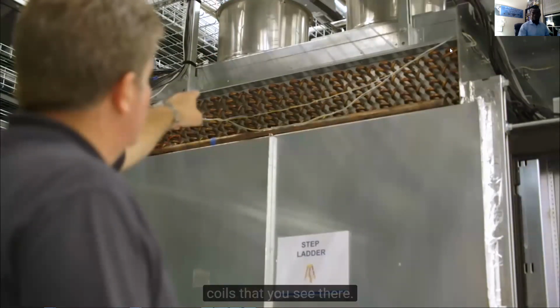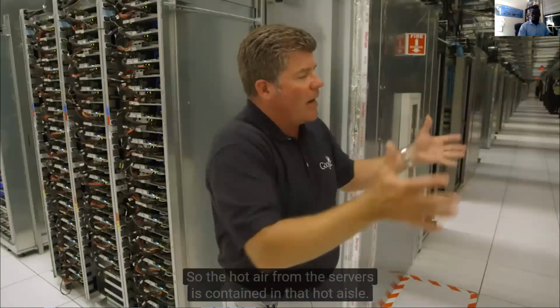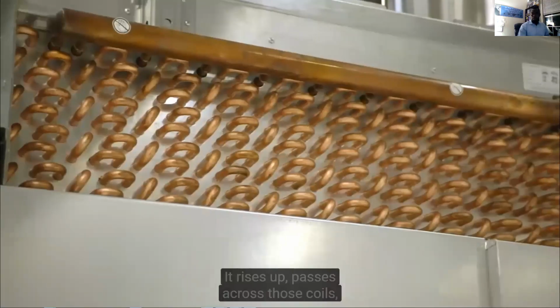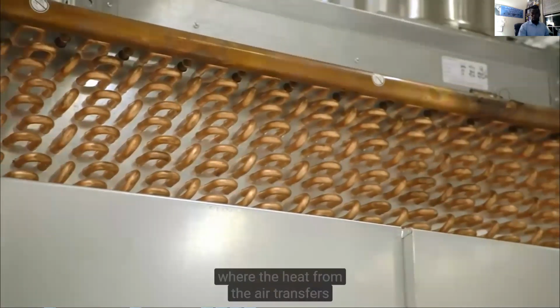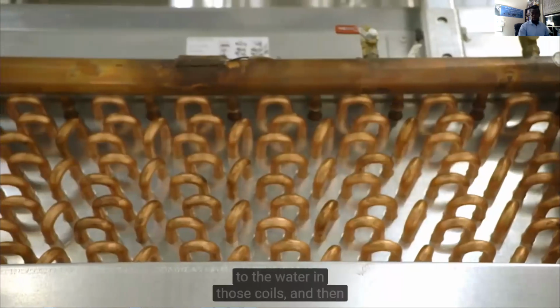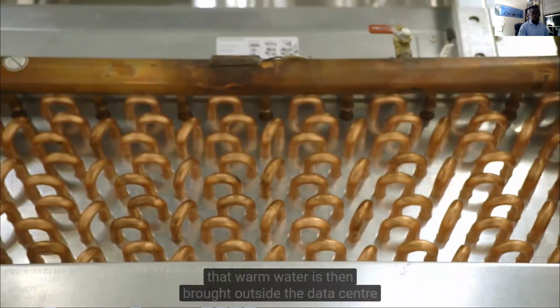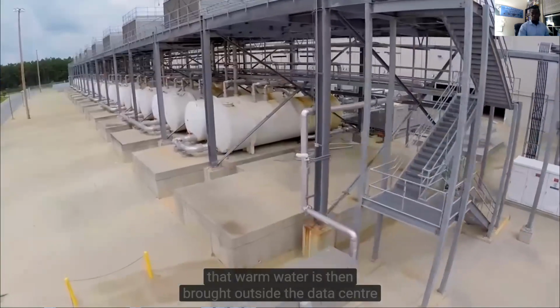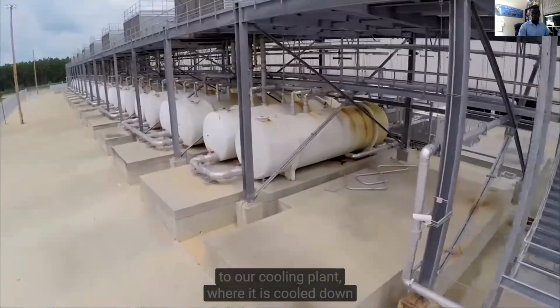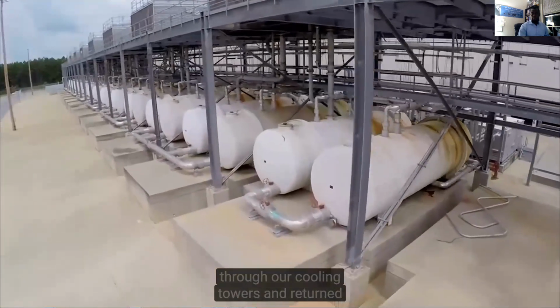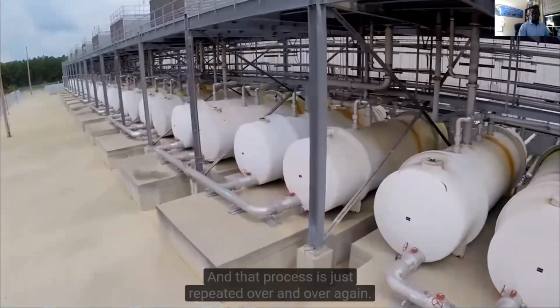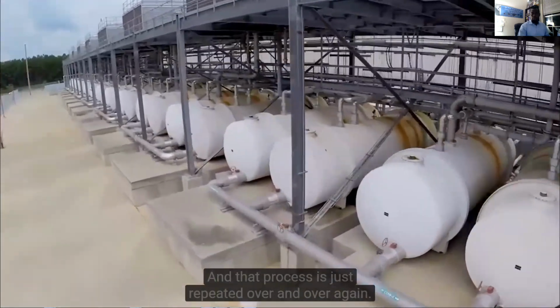So the hot air from the servers is contained in that hot aisle. It rises up, passes across those coils where the heat from the air transfers to the water in those coils, and then that warm water is brought outside the data center to our cooling plant, where it is cooled down through our cooling towers and returned back to the data center, and that process just repeats over and over again.